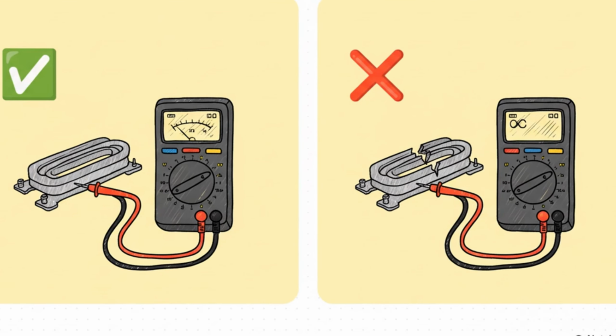Okay, for test number one, the continuity check, you're just going to touch your multimeter probes to the two main terminals on the heater. A good, healthy element will give you a resistance reading somewhere between 10 and 50 ohms. But if your meter shows OL for open line, that means the pathway inside is broken. The part is toast, it's done.